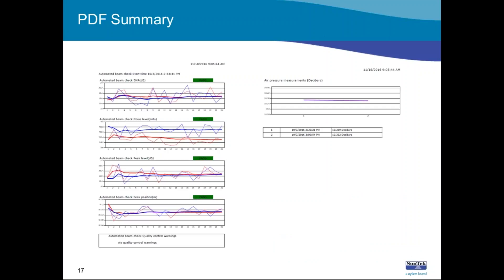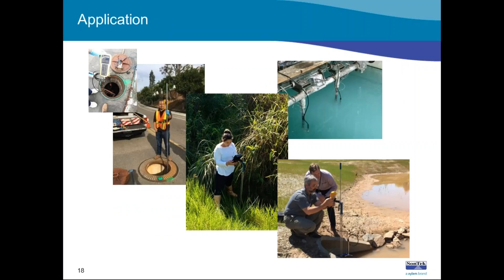A PDF discharge measurement summary comes out of the FlowTracker 2 software. All of this data is packaged in a nice PDF report with graphics, including the beam check shown on the left-hand side. The beam check monitors the health of the instrument — whether your signal strength is adequate and signal characteristics are adequate — providing a further QC check. Now that we have a pressure sensor, we can show pressure data in graphical form as well, with the pressure summary on the right-hand side. That measurement that was taken did change over the course of the measurement, so this isn't just theory.